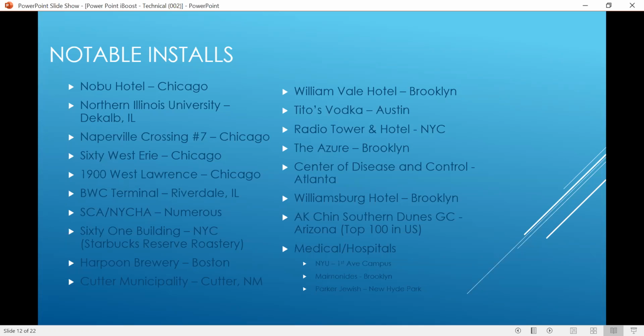On the hospital systems, I'll just say a couple of comments. They're probably the systems where we can really accommodate that customer. They have several needs. I know you guys have the seismic rated panels out there, which we can do. We can also do 100% redundancy on each pump if that's what they need. And we can also do the building controls to match up with whatever they have in there.